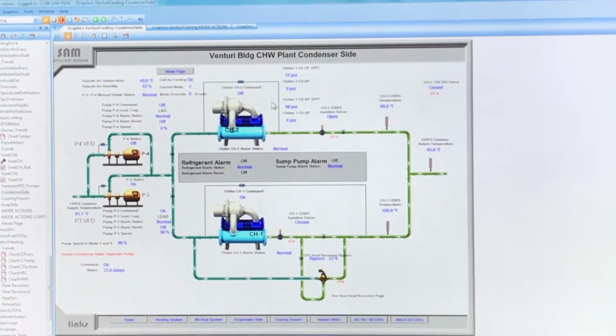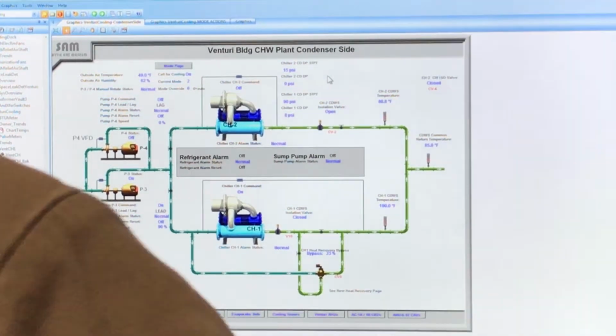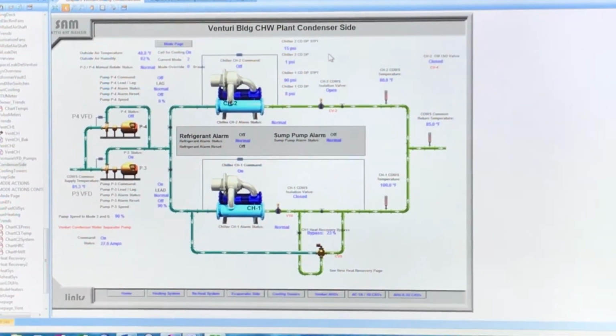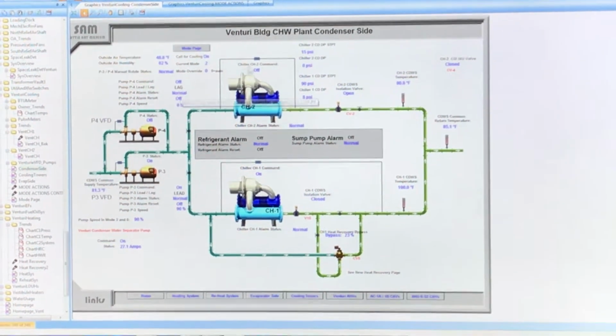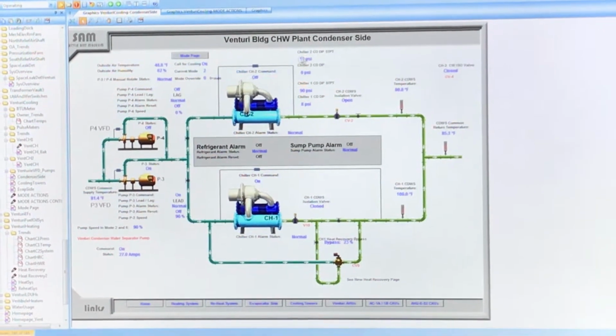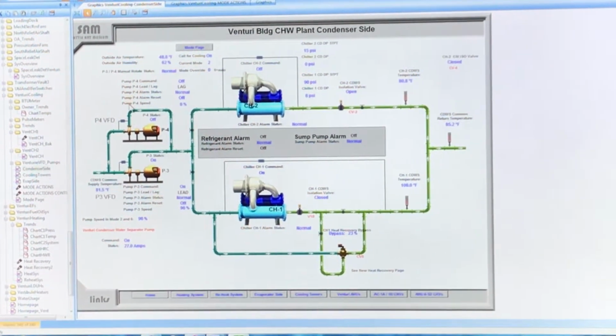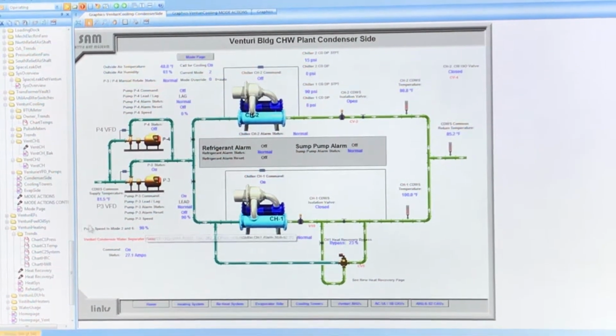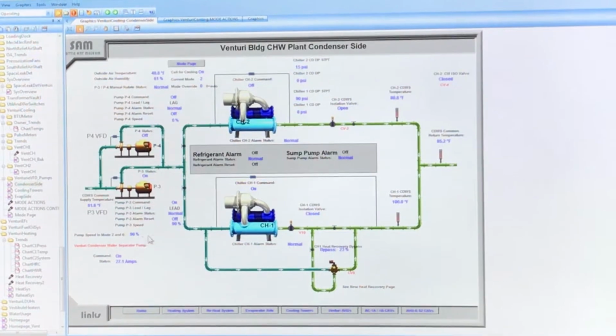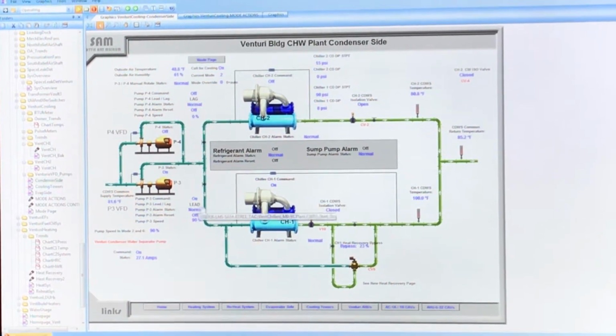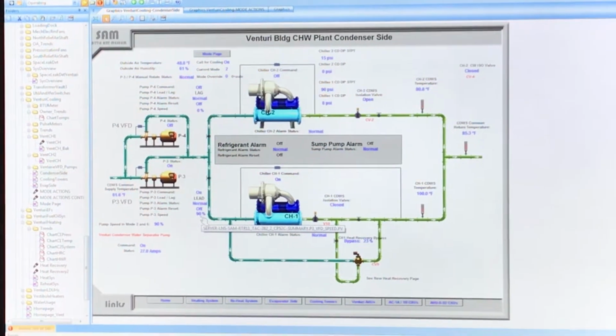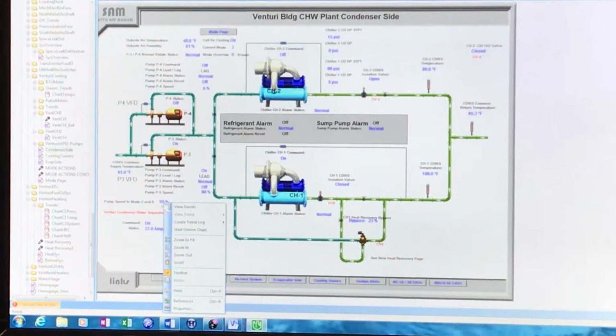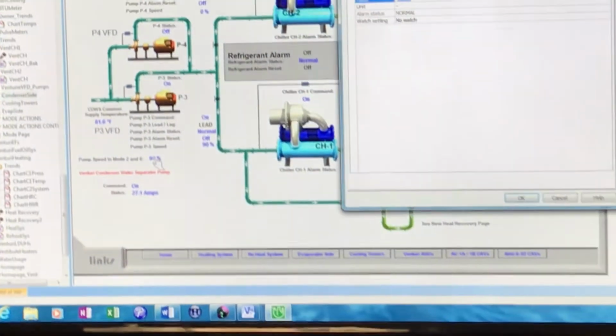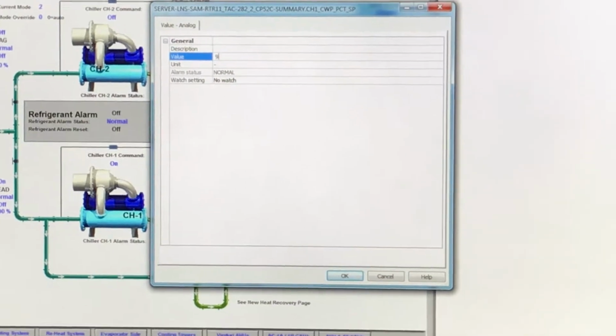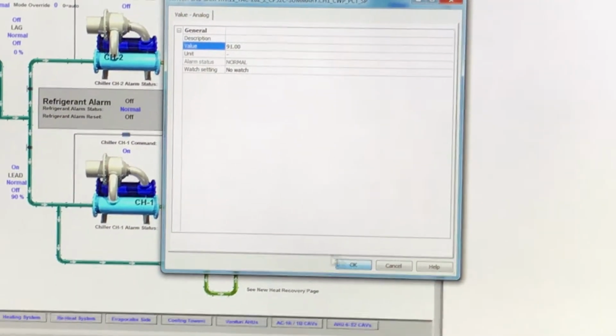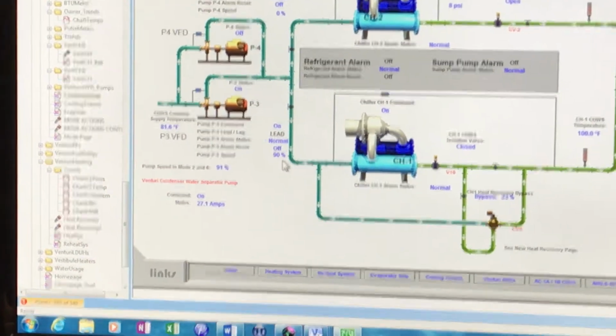And for the tower, I think there's a design minimum. We can look at that later. It uses the differential to control the pump's speed, and there's also a set point here for pump speed in mode 2 and 6. It's a set speed. Right now it should be 90%, which it is, right here. You can change that by just clicking on it. But that value comes from the balancing work. Yeah, from the balancing work. So if I change that to 91, this is going to jump up to 91.